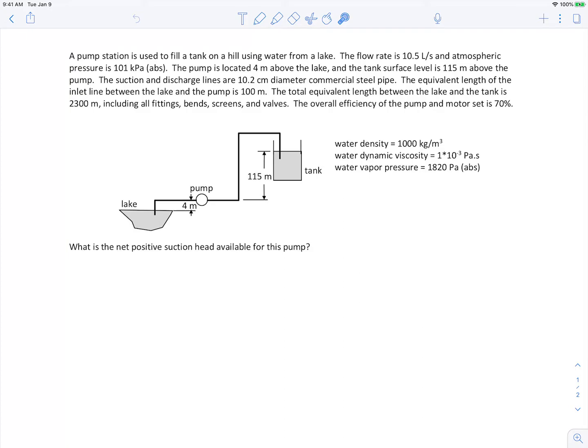The equivalent length concept means you replace the fittings, bends, screens, and valves with an equivalent length of pipe that gives the same major loss as the minor losses. So with an equivalent length of 2,300 meters, when we calculate the major loss for that distance, all the minor losses are included inside it. We're also told the overall efficiency of the pump and motor, and that we're dealing with water with those properties.